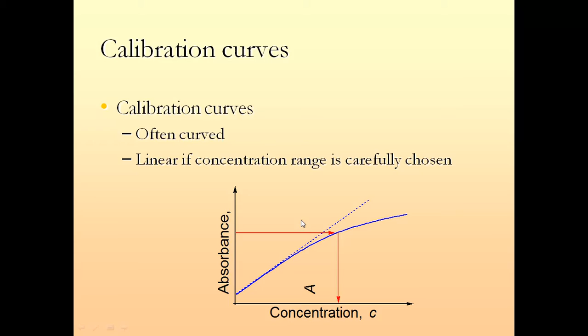During the calibration, it should not always be curved when you increase the concentration, but basically it should be linear if the concentration is rightly chosen. So here, when we are doing the analysis, first we should have a blank sample, then we have 3 reference materials, 5, 10, 15 ppm, then we have an unknown sample.